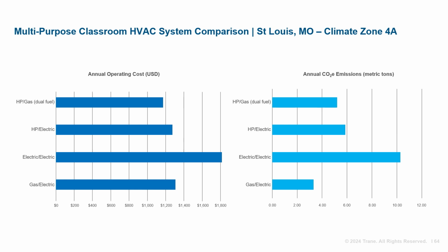Due to the utility rates used, a heat pump with natural gas auxiliary heat saves approximately 9% in annual operating costs, but due to the SRMW grid emissions factors, the CO2e is 58% greater than the baseline gas-electric rooftop unit on an annual basis. Utility rates and the cleanliness of the utility grid can play a factor in unit selection. If the owner's goal is to decarbonize, then a traditional gas-electric unit results in the lowest CO2e.